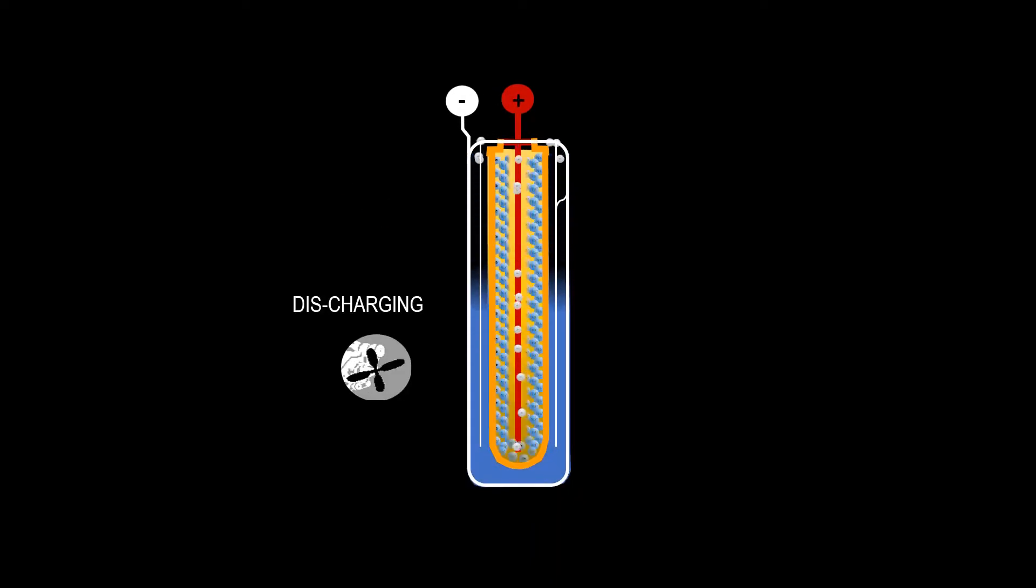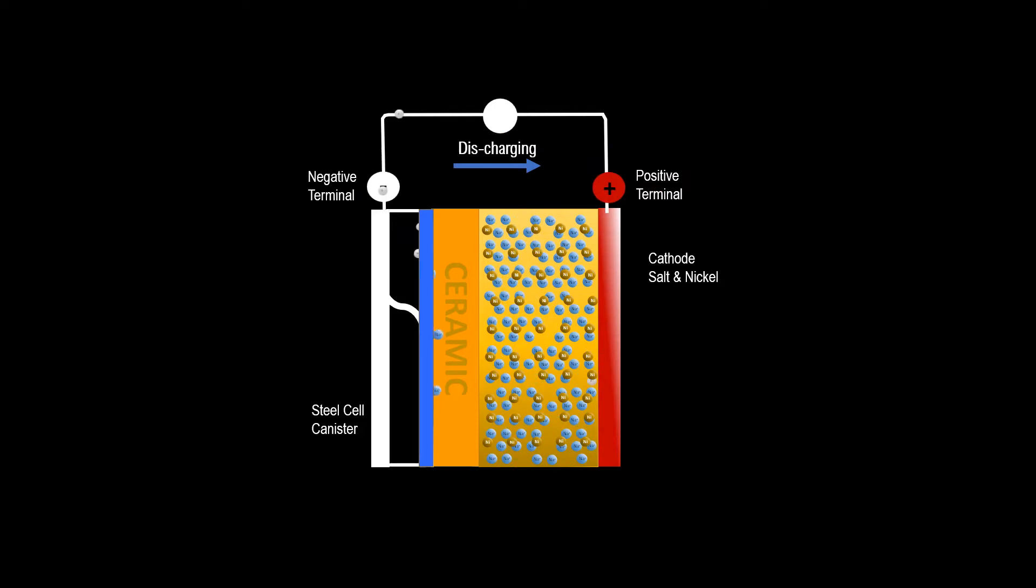During discharge, electrons flow back to the positive terminal, while sodium ions transfer back through the ceramic tube to the cathode section, joining once again with the chloride and transforming back into salt.